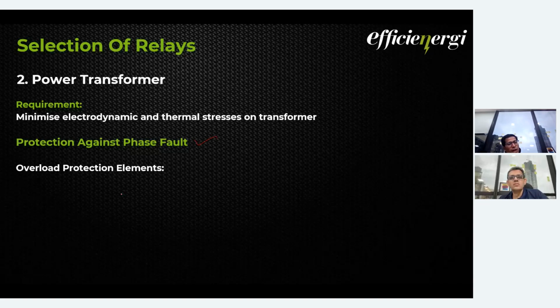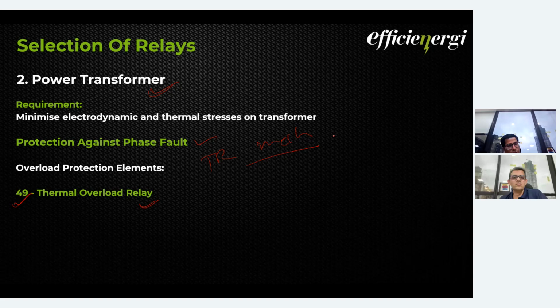So for a transformer, we are looking for a 49 thermal overload relay. In a power transformer, we can have this thermal overload. Basically, in a transformer, we also have mechanical relays. Mechanical relays means Buchholz relay and pressure sensitive relays. Those are mechanical relays, used for internal faults. We're also using a temperature sensor here. The temperature sensor and thermal overload should have almost similar characteristics.